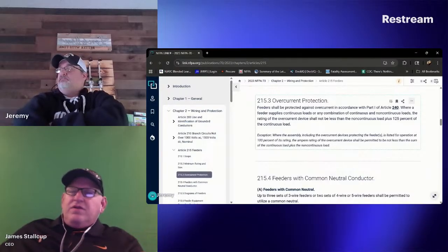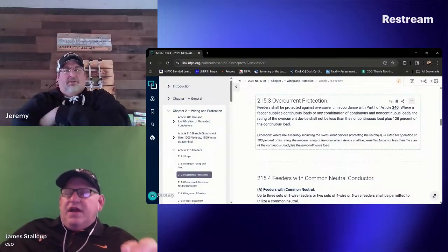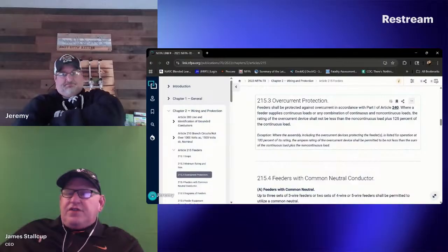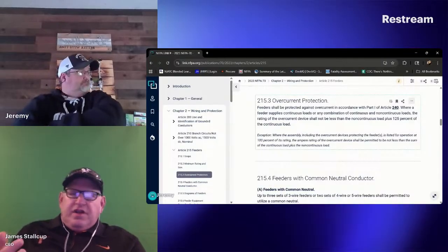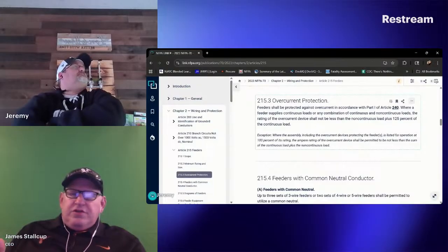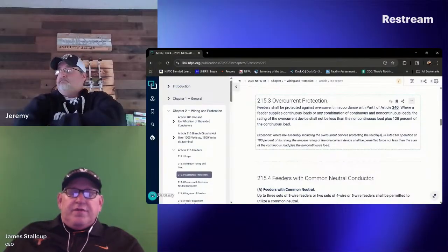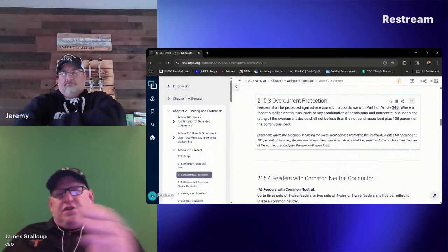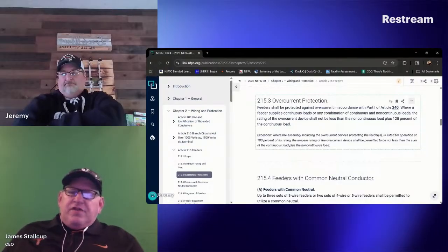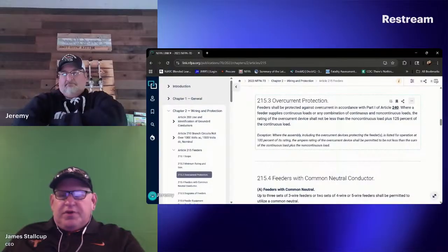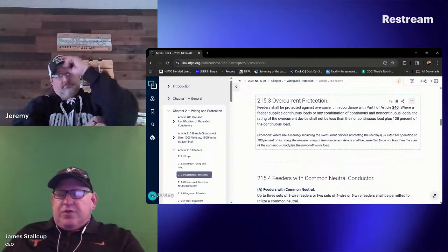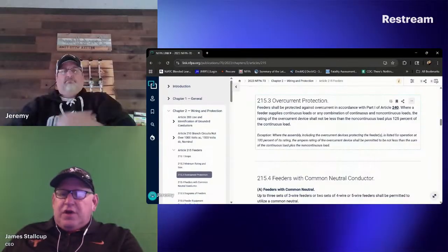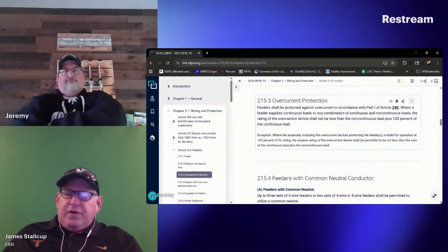It doesn't matter. Hold on, let me finish. It doesn't matter if I do branch circuits, feeders, or services. I'll give you all the sections. Go look at 210.19A1, 210.20A, 215.2A1, 215.3, and then go look at 230.42A1. They're all exactly the same when you go into sizing this. Once you do all your sizing for the conductors, you go over and look at sizing your overcurrent device. All the same rules are in place for sizing at 125% or 100%. Then you go over to Article 240 and your rules are there for your overcurrent protection device.